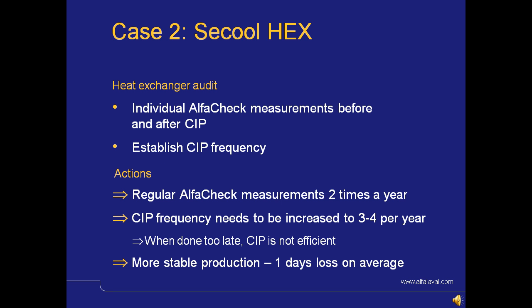Again, in order to assess the situation fairly, we proposed a heat exchanger audit. We did individual AlfaCheck measurements on each and every heat exchanger before and after the chemical cleaning. This was done in order to assess and quantify the actual result of the cleaning. When you do CIP, you do not open the heat exchanger, and this sometimes means that you cannot confirm how well the heat exchanger has been cleaned without doing the AlfaCheck measurement.